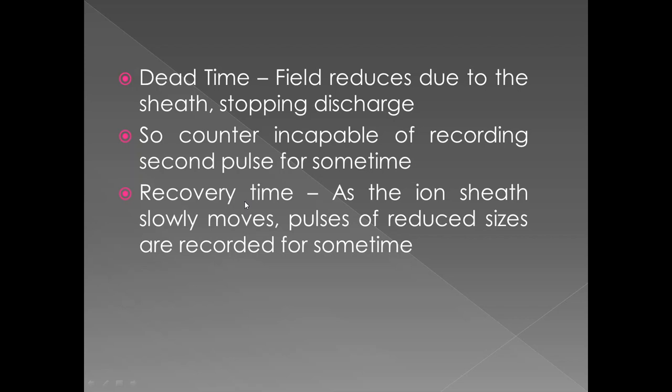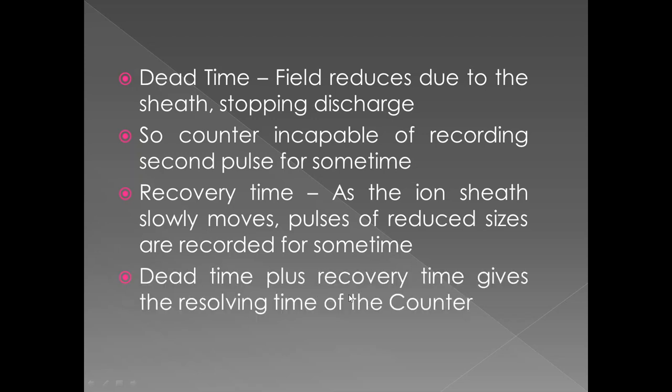So another aspect is the recovery time. As the ion sheath slowly moves towards the cathode, the ions get neutralized and slowly the electric field builds up. There is a time between the ionization stopping and the electric field attaining its final strength. In between, pulses of reduced sizes are recorded for some time. This time is called the recovery time, from the point when the ionization stops till the electric field reaches its final strength. So the dead time plus the recovery time gives the resolving time of the counter.